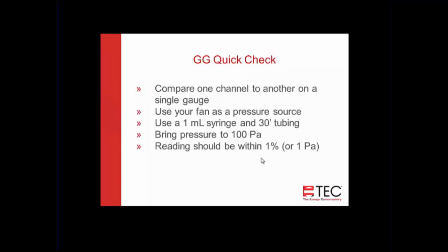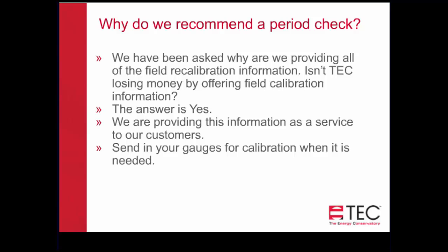It can be just sitting in the middle of the floor, it doesn't need to be connected up to anything, and run it up to 100 pascals, and channel A and channel B should be within 1 pascal of each other. So that would be 1%. And it doesn't say your gauge is within calibration. It's not a calibration check, but it's just a quick check to see if there's a large error on one of your channels. Hopefully that information was useful for you.